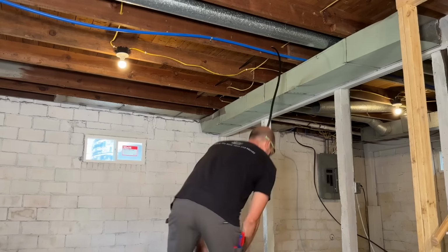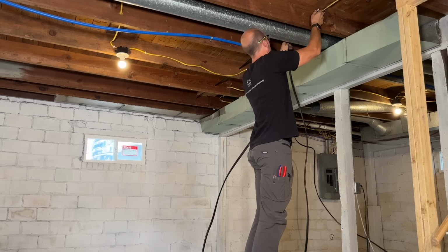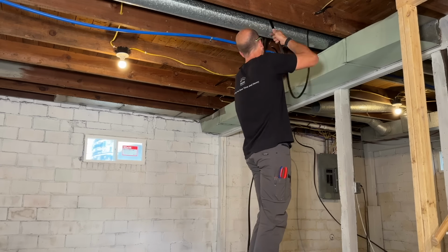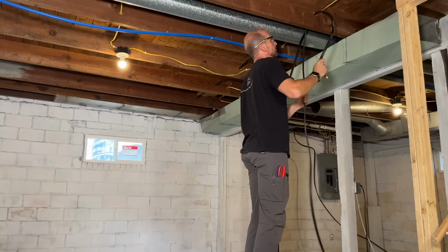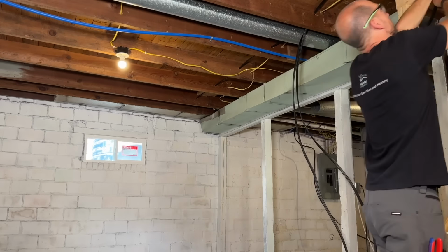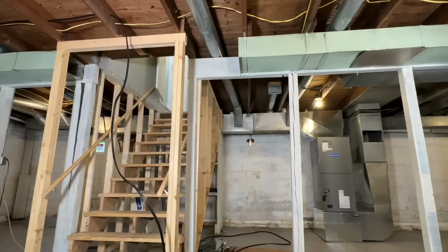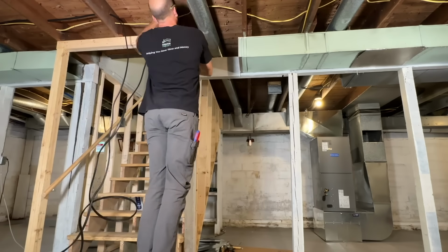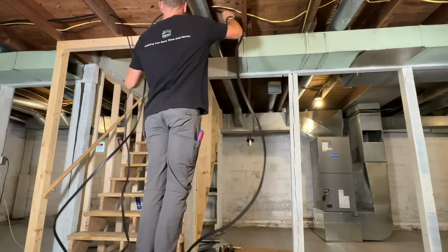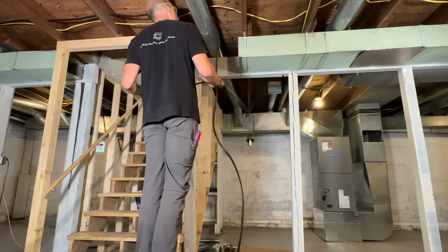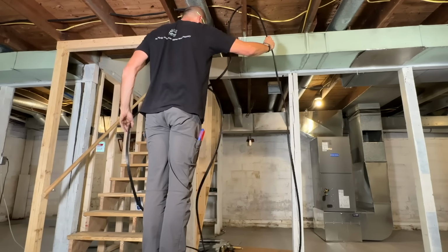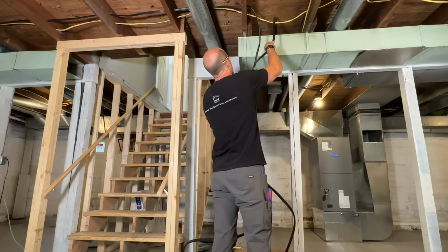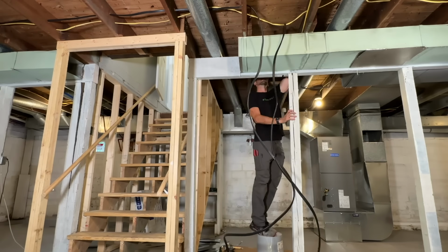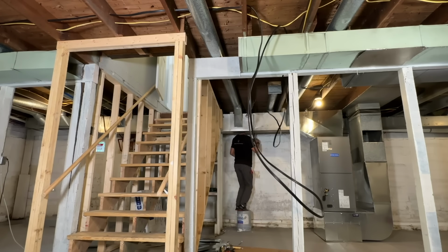Things like that ductwork there, you're going to have to kind of snake over and maybe just do one joist at a time, but you'll be able to work it across the room if you're going through a basement such as I am here. Each one of our setups will be a little different. So once I get it over to the appropriate joist, then I'll just run it right in the middle. You can see that LB conduit body that I'll then run over to, and I'll use large staples to secure the Romex on the side of the floor joist.